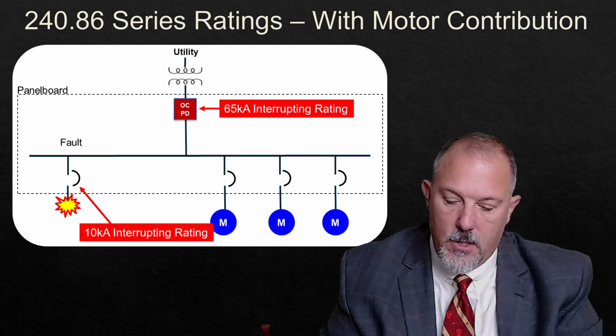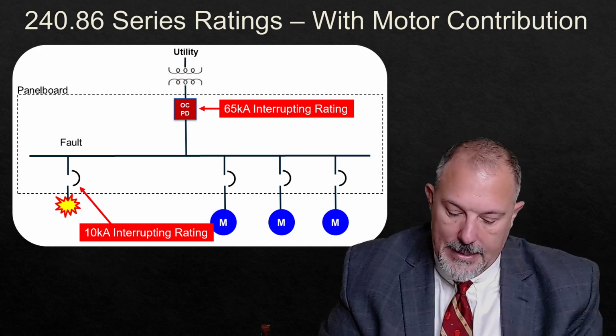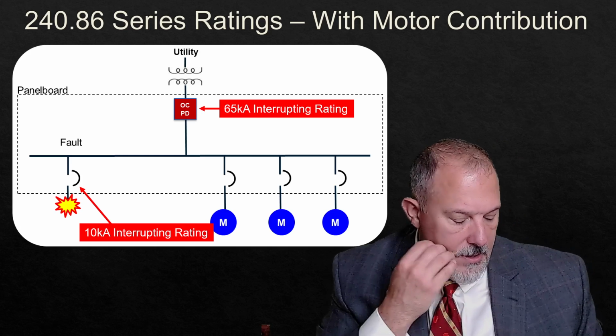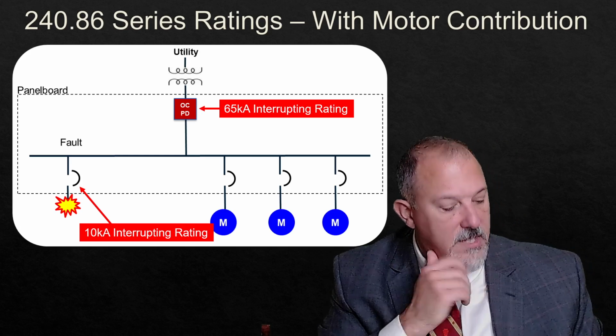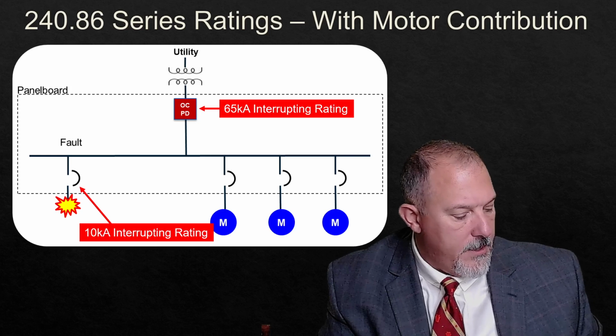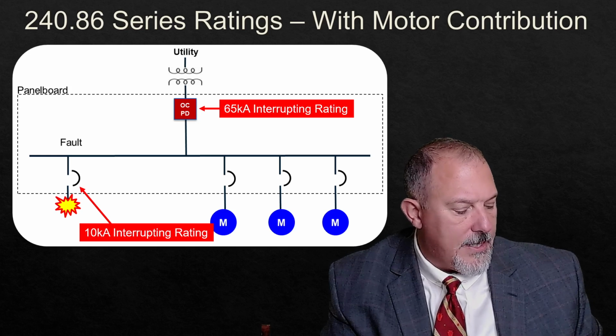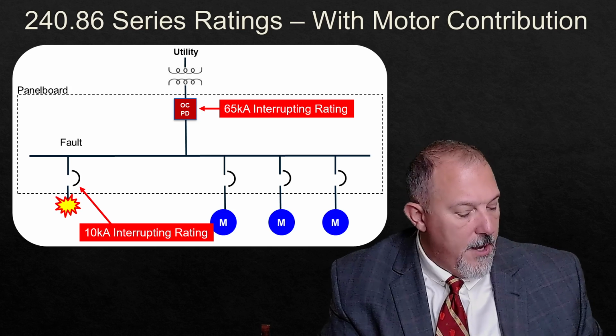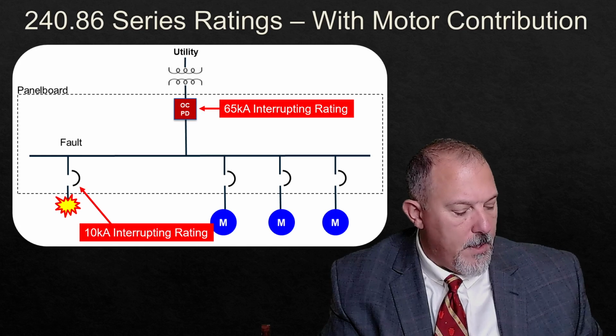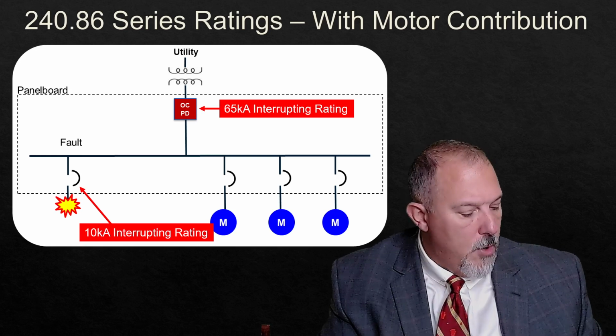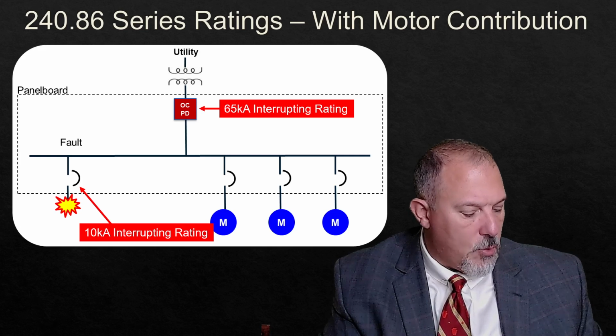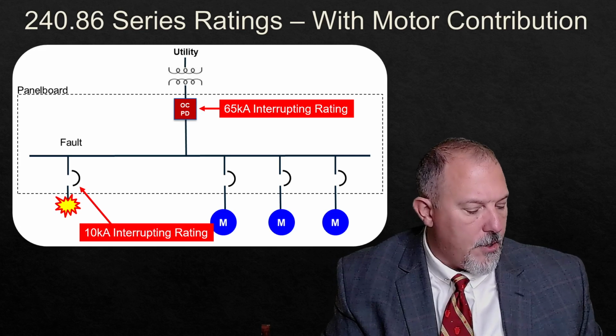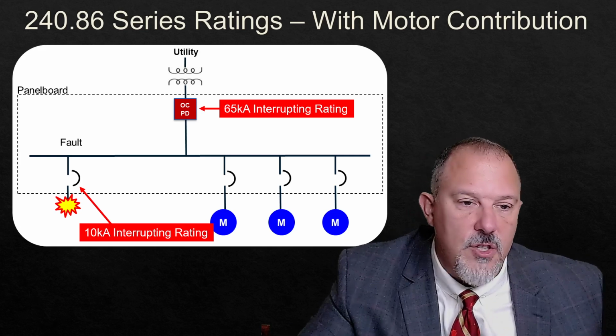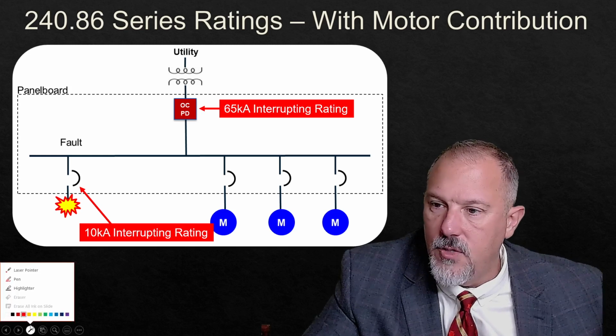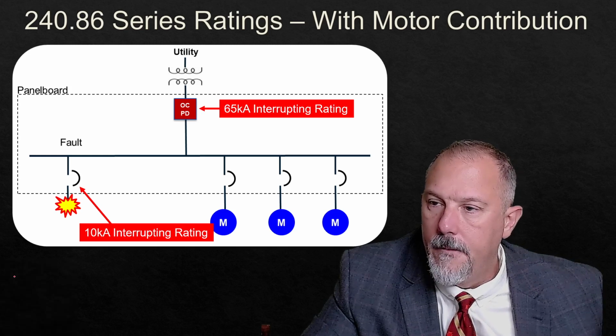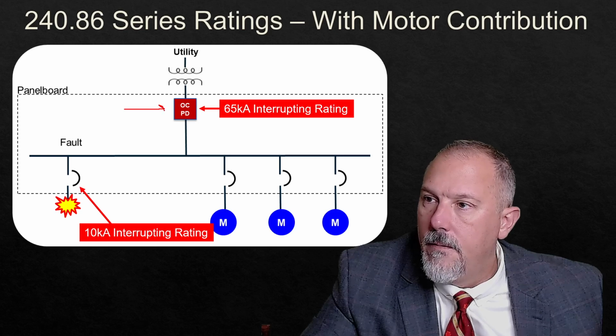240.86. 240.86 is series ratings, and it'll tell you in 240.86.C, motor contribution, the series ratings shall not be used where motor circuits are connected between the high-rated overcurrent device. So between the high-rated overcurrent device, which is where? Right there. That's the high-rated.